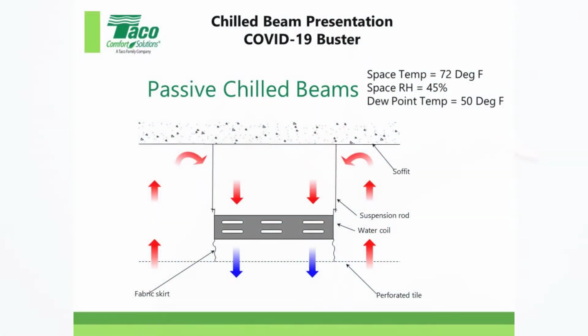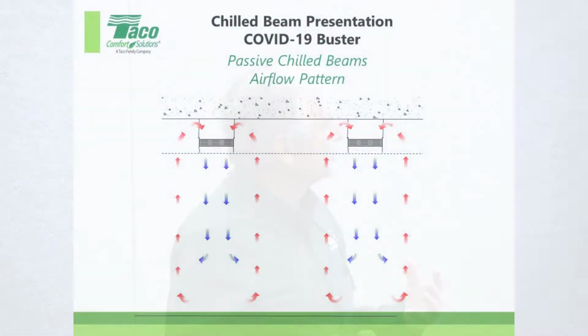And here's the actual flow in the chill beam, and you can see the cooling comes down. So it's a very subtle, very slow type of setup. That's what you could expect from a passive chill beam. Let me go back there. You can kind of see what you could expect in a room. If you ever do get on a project working with a system like this, work with a chill beam manufacturer. Find one that you're comfortable with. They have a lot of programs that can help lay it out in the building, or the zone, or the room. That's what our mechanical team did when we designed our building. They come with lights now, drip pans. There are all kinds of gadgets that the chill beam manufacturers have. But there's the gentle flow you could expect from a passive chill beam. Very comfortable, very quiet.